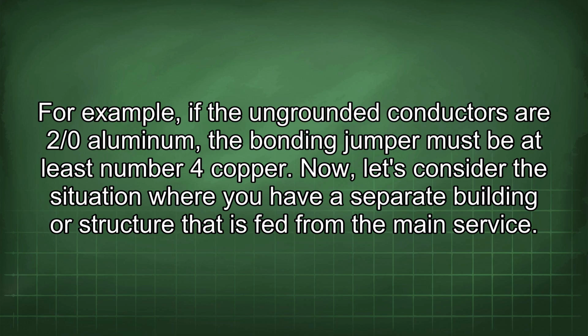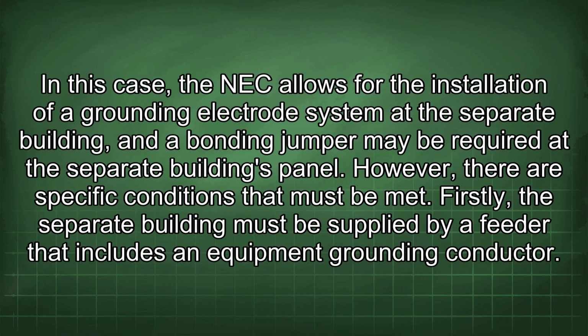Now, let's consider the situation where you have a separate building or structure that is fed from the main service. In this case, the NEC allows for the installation of a grounding electrode system at the separate building, and a bonding jumper may be required at the separate building's panel. However, there are specific conditions that must be met.